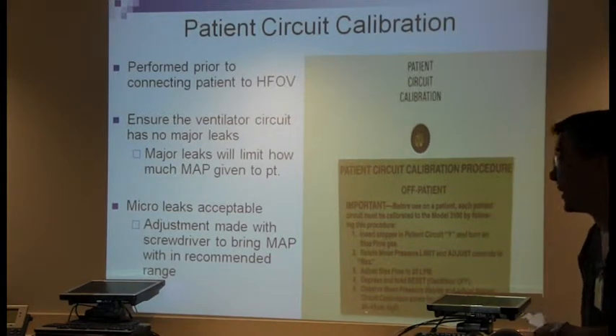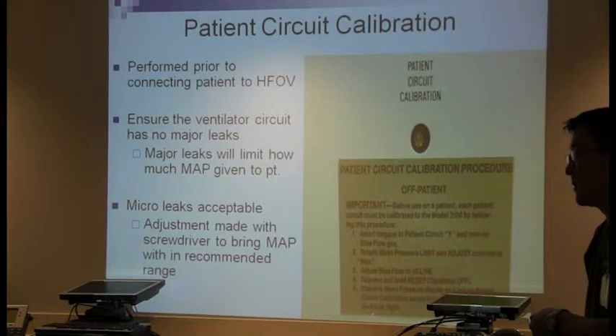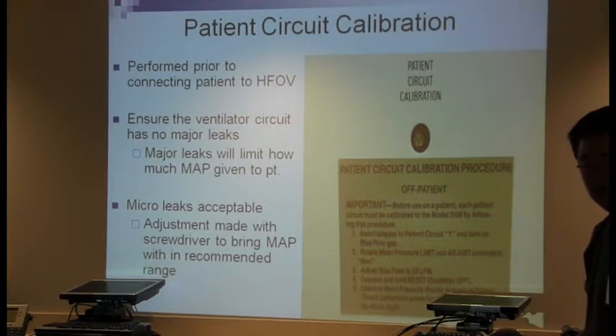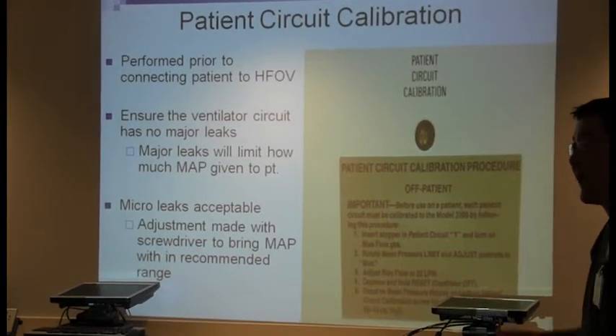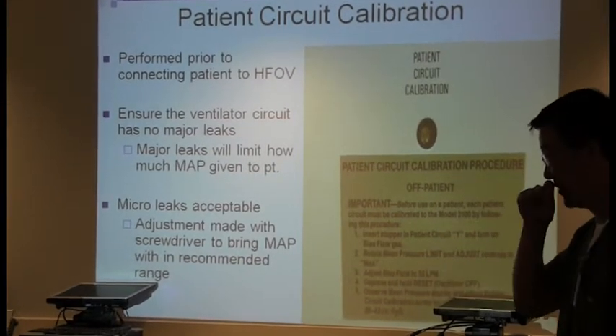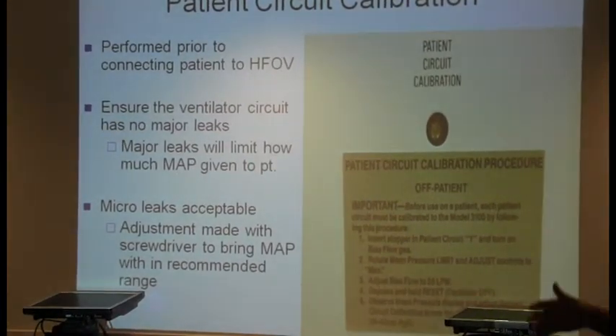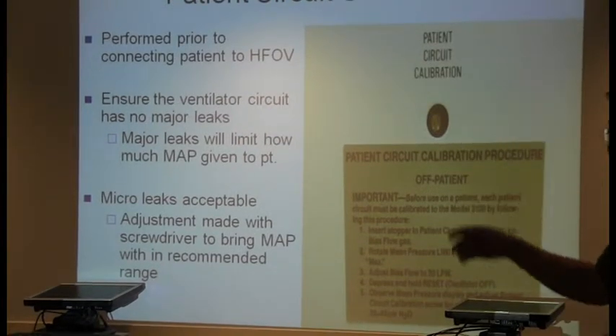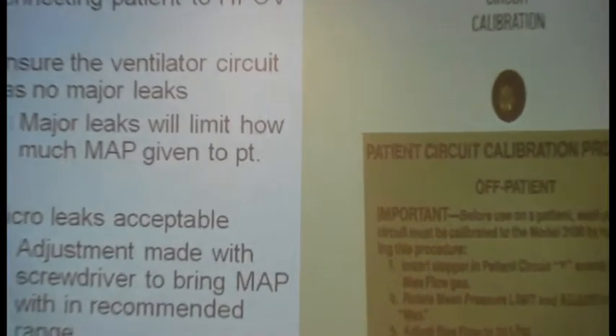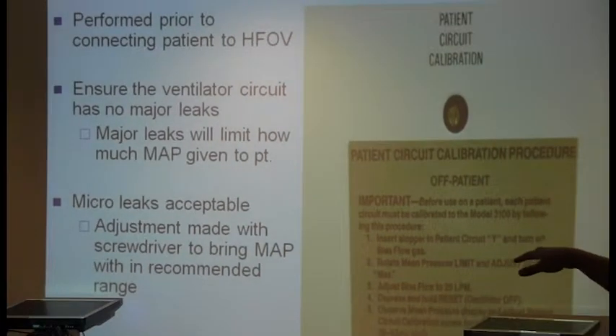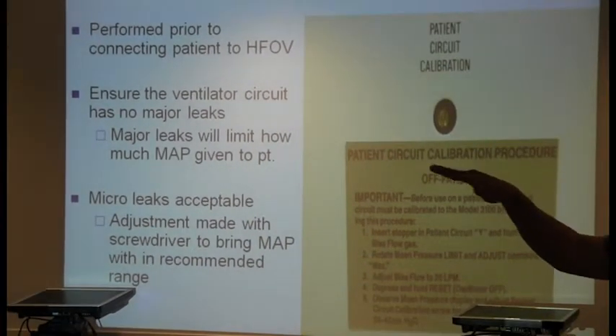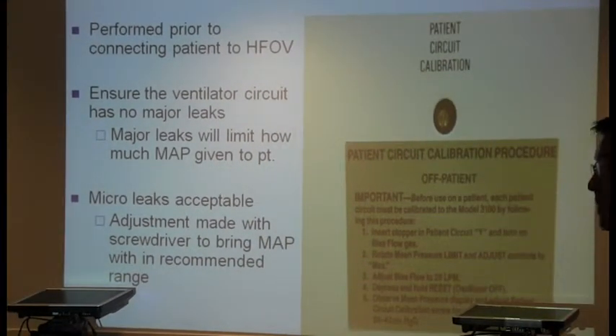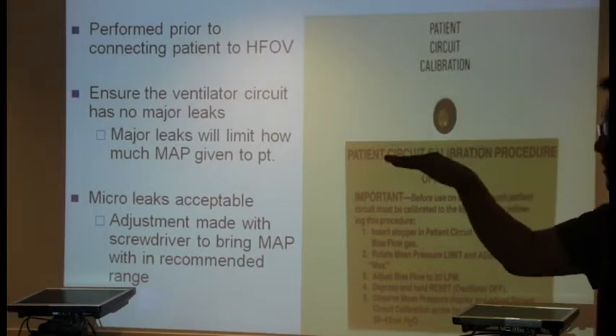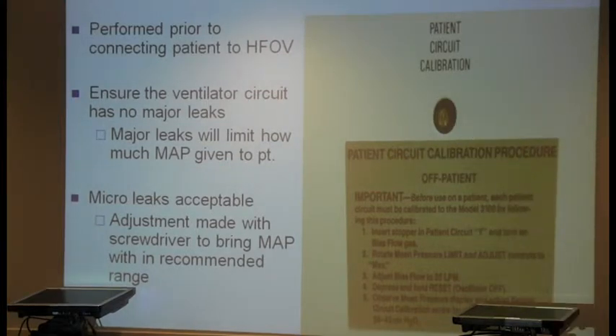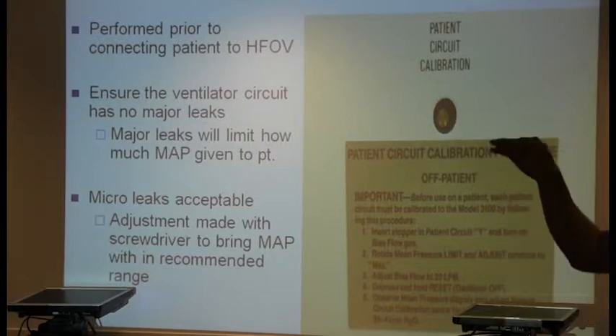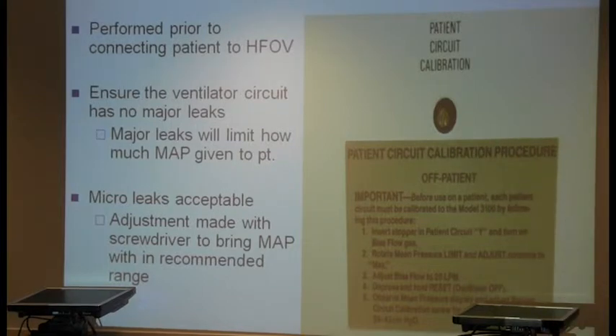If your bias flow is too high, what's going to happen to our mean readout? It's going to be high, because we added more flow, so more resistance, so we're going to have a higher mean because you added too much bias flow. So be careful with your bias flow, because a lot of times the lower pressure is because our bias flow is not in the middle. People think it is, but when you look at it, the head of the ball is below the number 20. So once you crank it up from 15 to 20 in the middle, everything works perfectly.